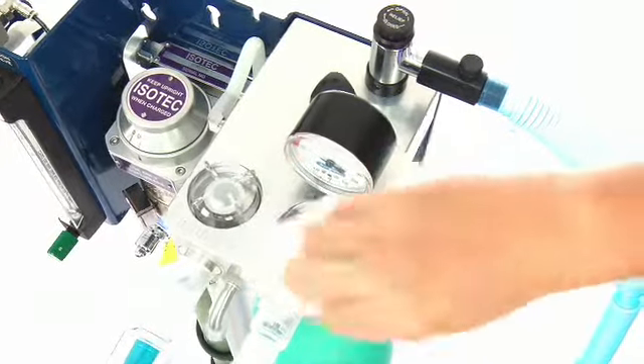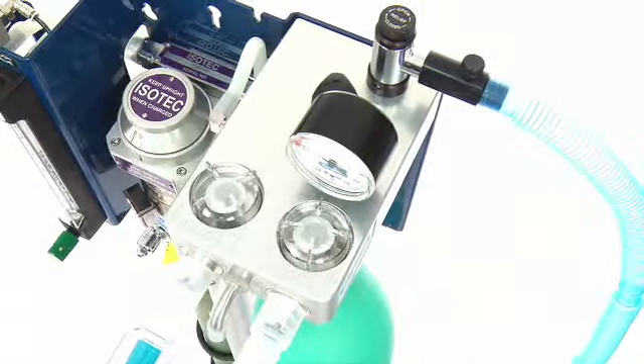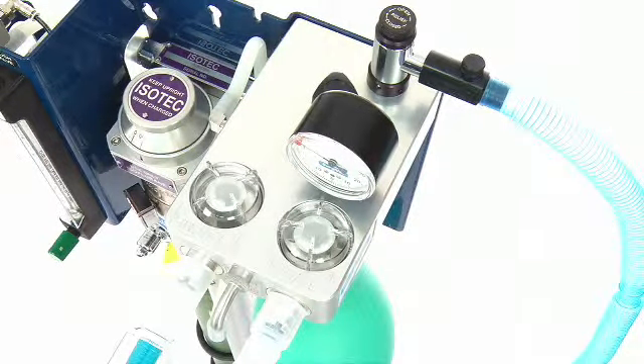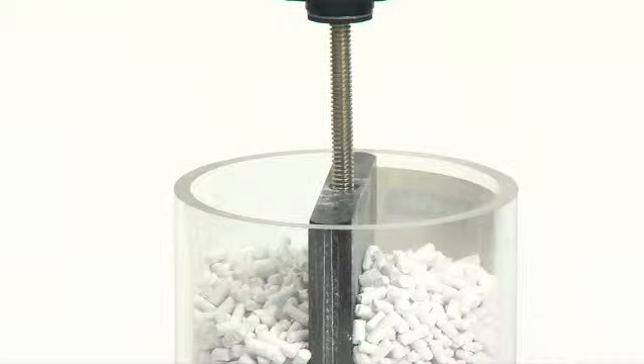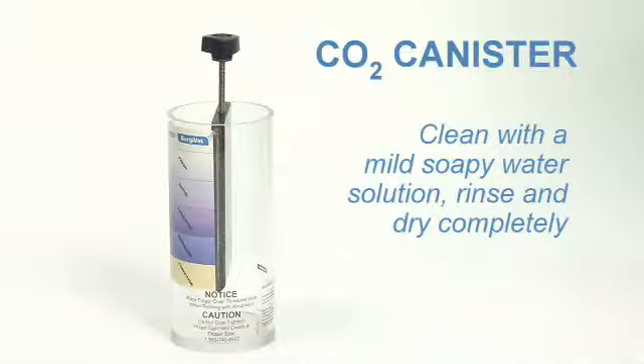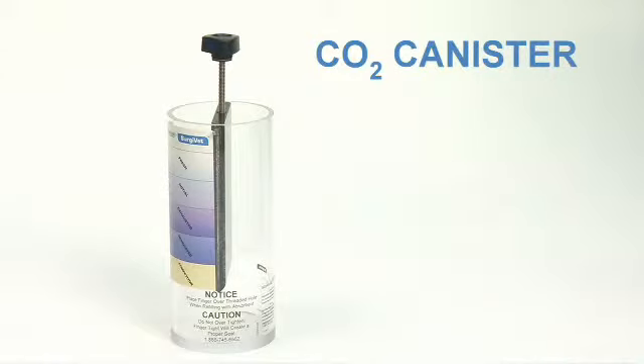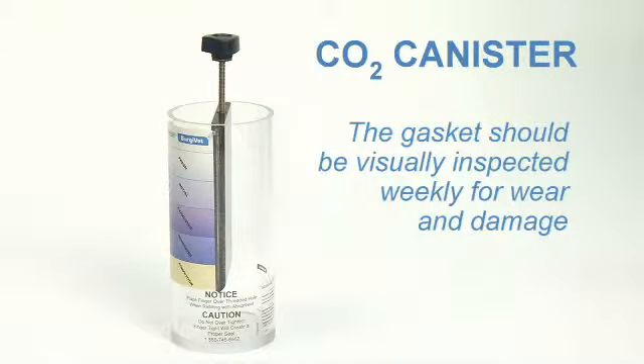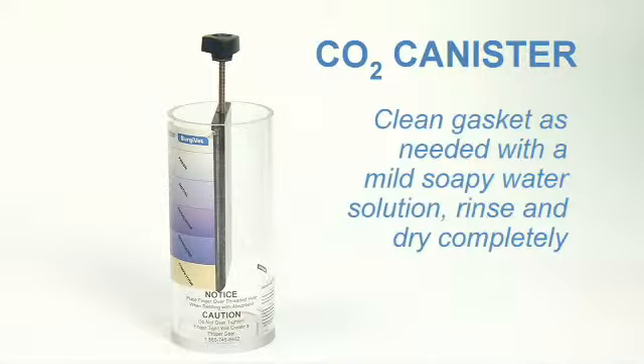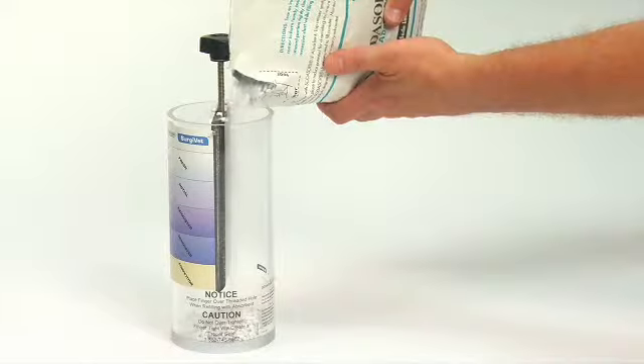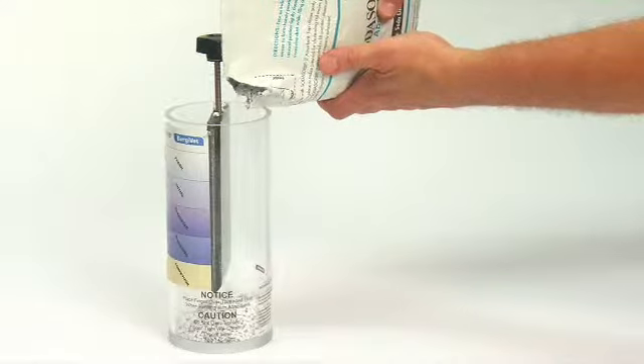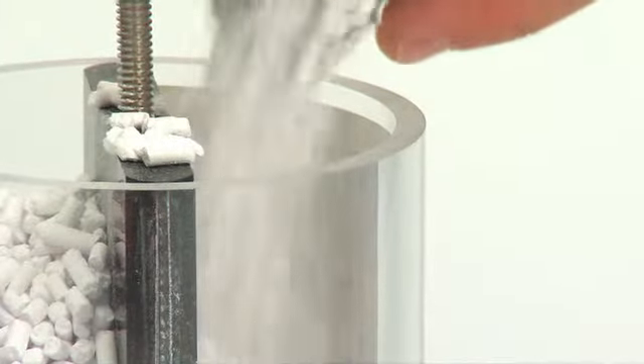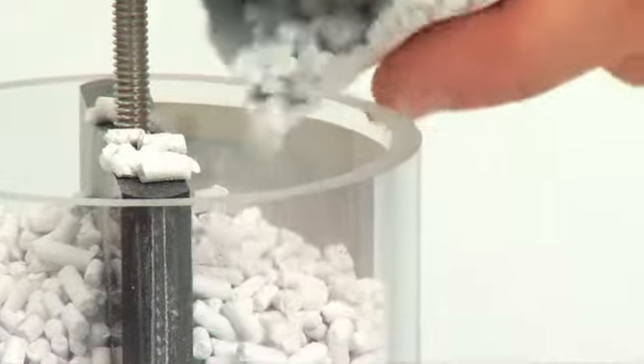The machine surfaces are recommended to be cleaned with a soft cloth and a mild soapy water solution daily, rinsed and dried completely. The carbon dioxide absorber canister should be cleaned as needed between changing out the absorbent granules. The canister should be cleaned with a mild soapy water solution, rinsed and dried completely. The gaskets to the canister should be visually inspected weekly for wear and damage. Clean as needed with a mild soapy water solution, rinse and dry completely. Change the absorbent as needed according to the manufacturer's directions. Leave 1/2 to 1 inch space between the granules and top of the canister to allow proper flow of gas through the canister.